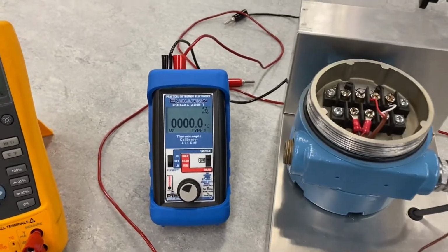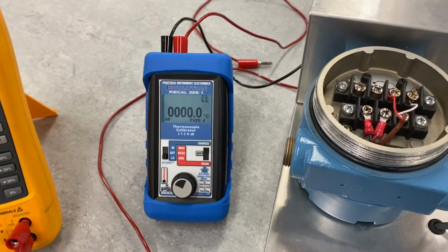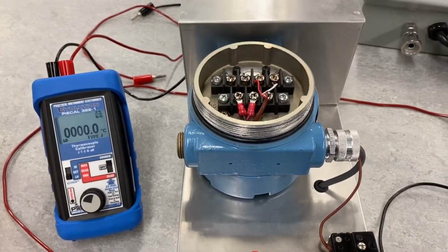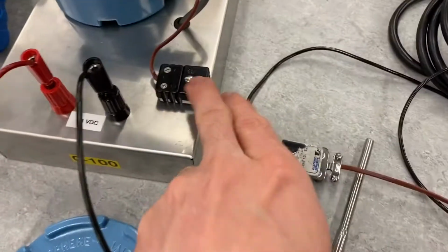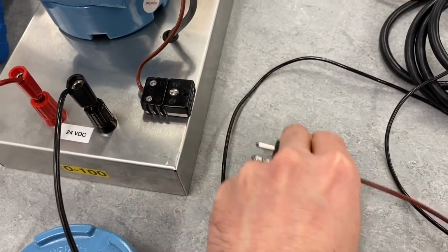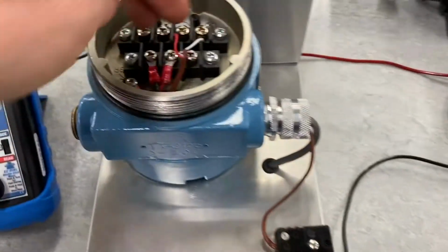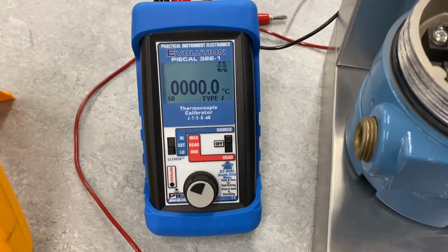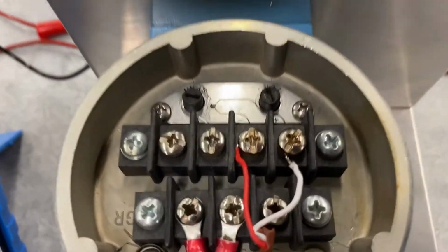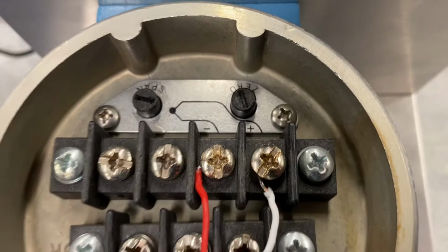So now to calibrate our transmitter, we're calibrating it for a range of 0 to 125 degrees C. I've disconnected the thermocouple here. We want to make sure we have it open here because we're going to be connecting the leads of our thermocouple calibrator. We're going to use the thermocouple calibrator now to calibrate it. We're going to be connecting across the positive and negative leads here. These wires can stay on.